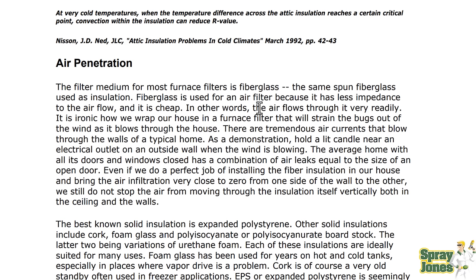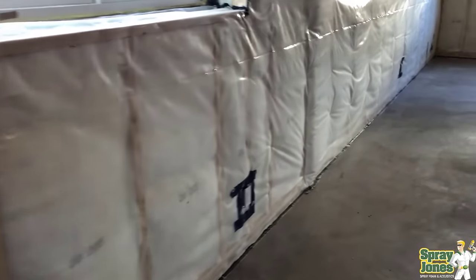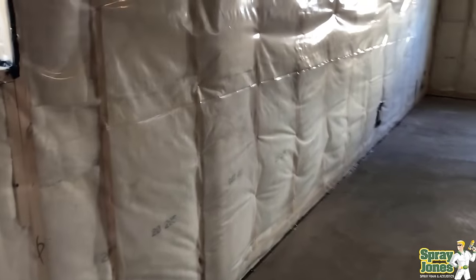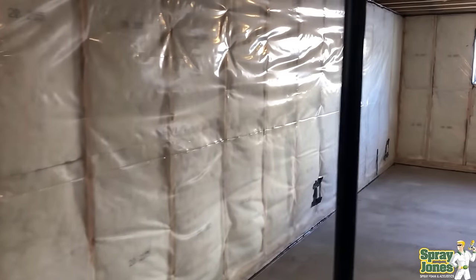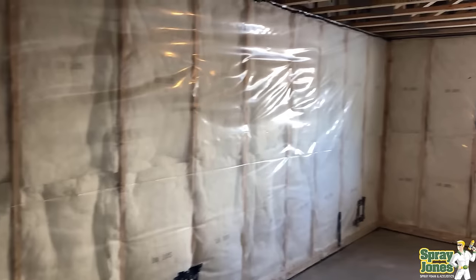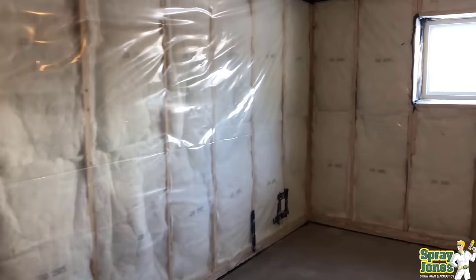Air penetration is a big deal. Fiberglass is used as an air filter because it has a low impedance to airflow — air flows through it very readily. It's ironic how we wrap our house in a furnace filter that will strain out bugs and wind as it blows through the house. A demonstration: hold a lit candle near an electrical outlet on an outside wall when the wind is blowing. The average home with all its doors and windows closed has a combination of air leakage equal to the size of an open door. We can get homes fairly well sealed until we put the sheetrock up.